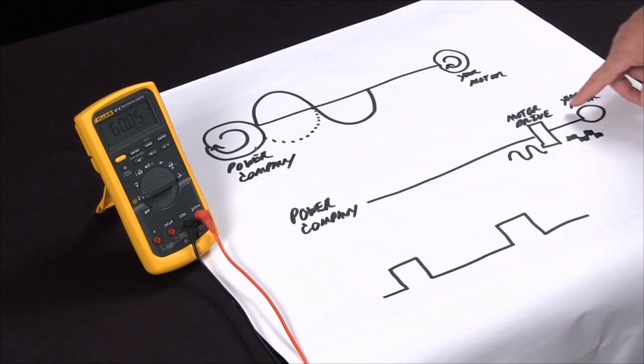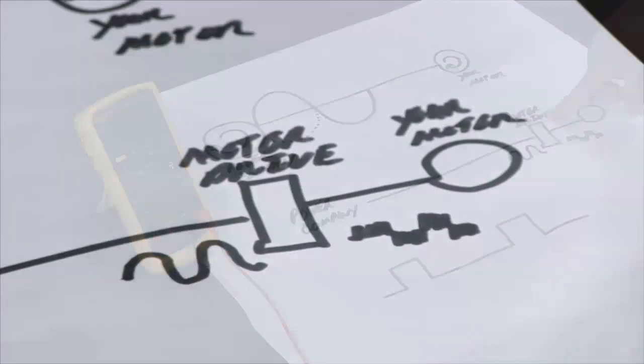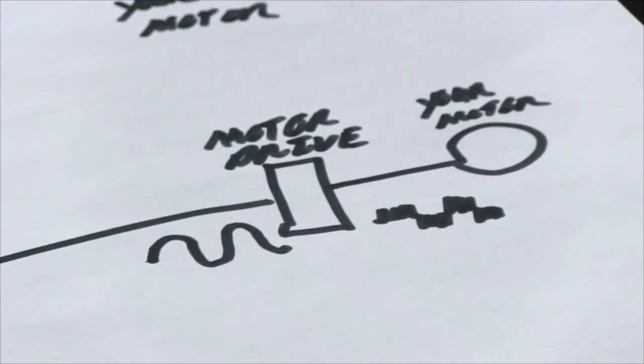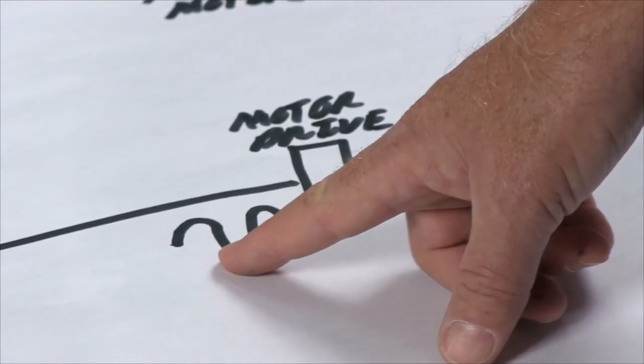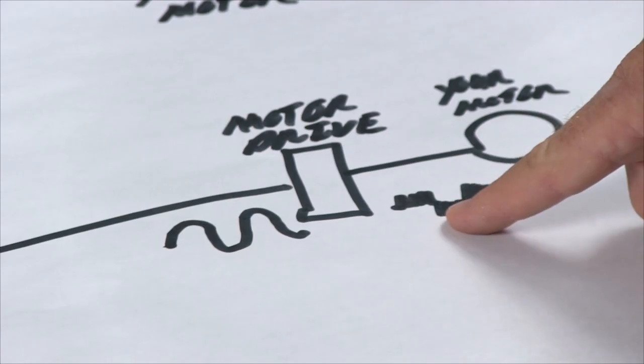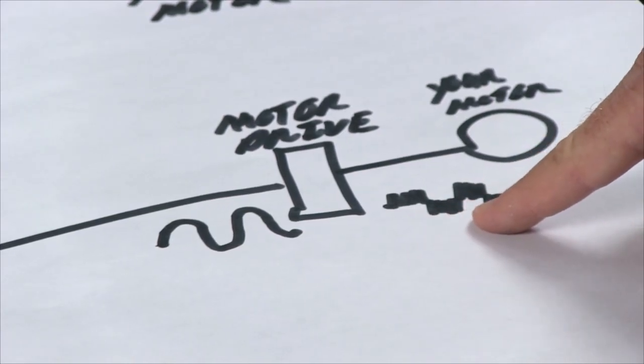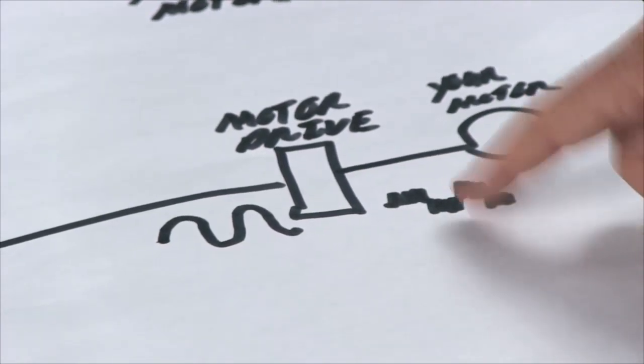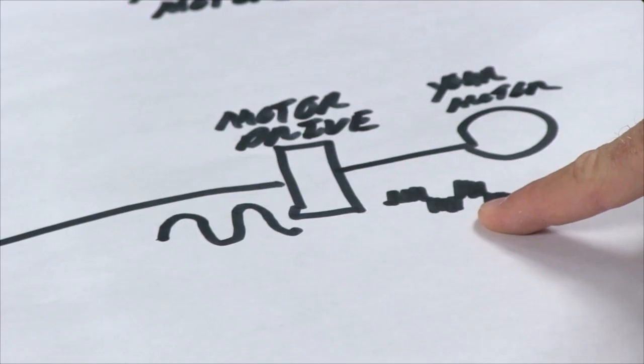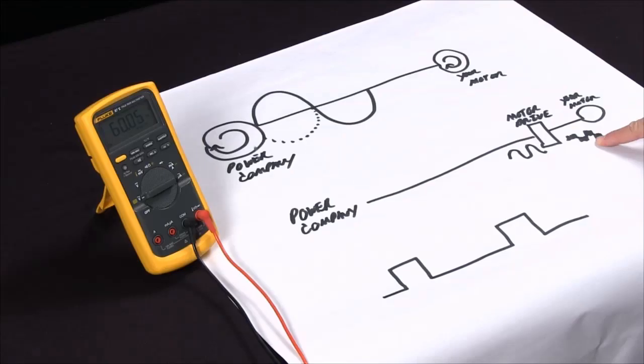As you get more into working with motor drives, this measurement becomes a little bit more complex because the motor drive takes your normal sine wave and puts it into a pulse width modulated or PWM signal. A normal multimeter is not going to be able to measure this frequency properly.